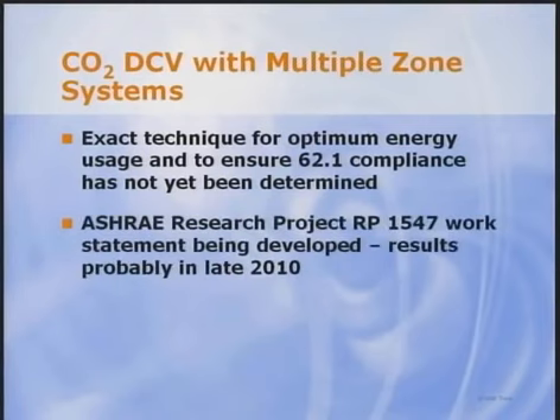The higher half of the CO2 range would be sent up to the air handler controller, where the largest signal from all DCV zones, those are the ones with CO2 sensors, would be mapped to increase the minimum outdoor air set point from the minimum required with no people in DCV zones up to the design outdoor air rate. The reason why we feel this is efficient is because in mild weather, the economizer will be operational, so all zones will be well ventilated. All will be in the lower half of their CO2 ranges. Under this condition, there's little added reheat energy and no added air handler cooling or heating energy.